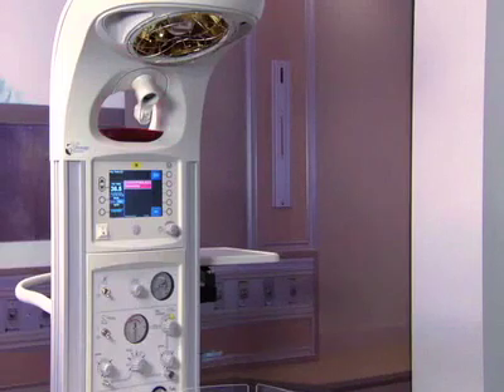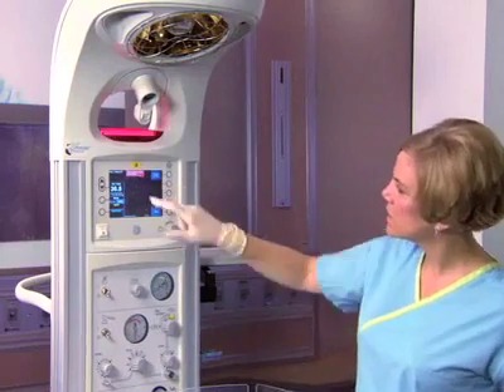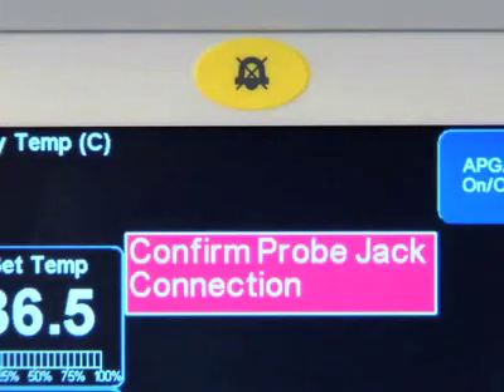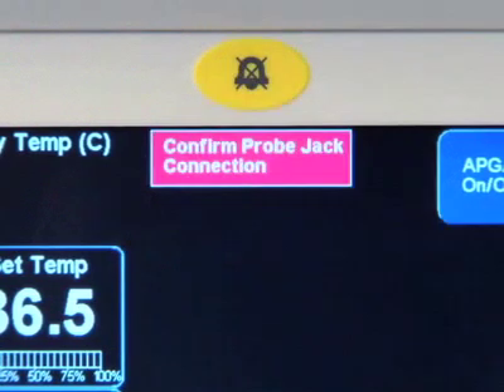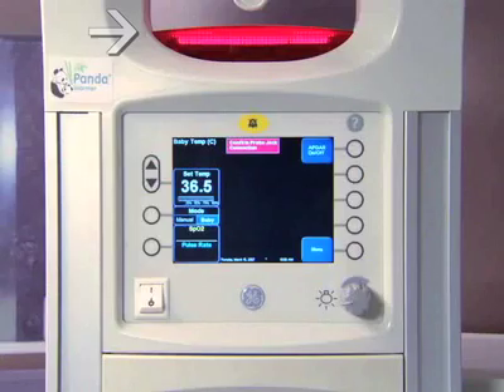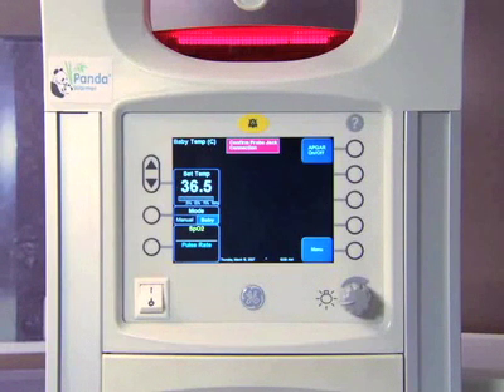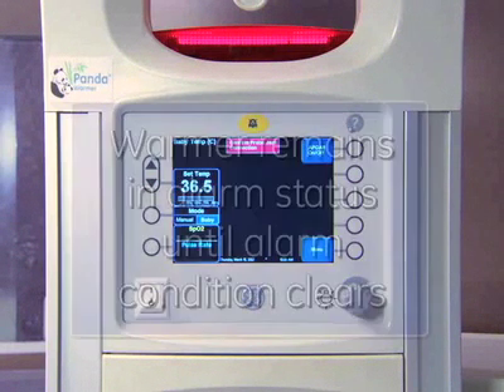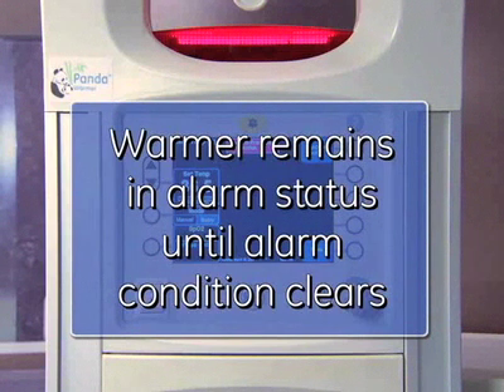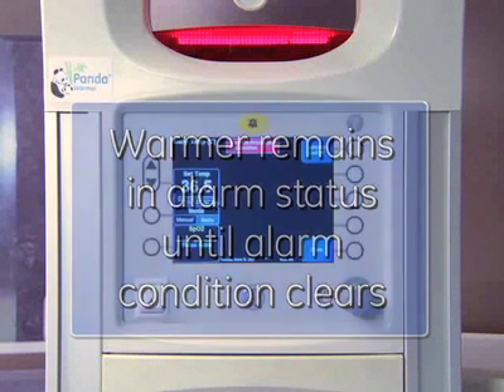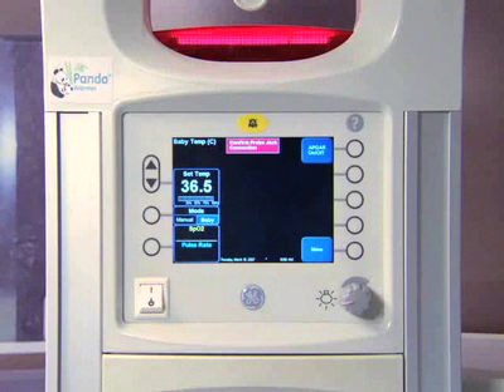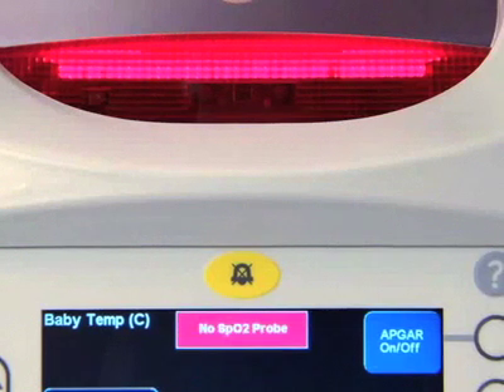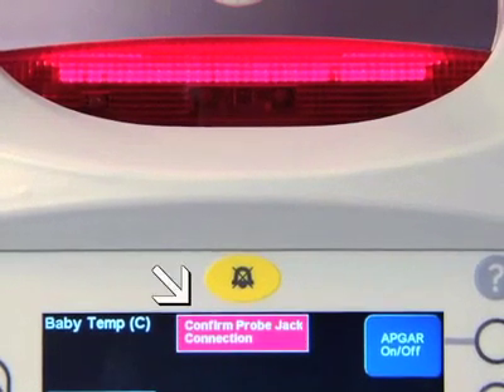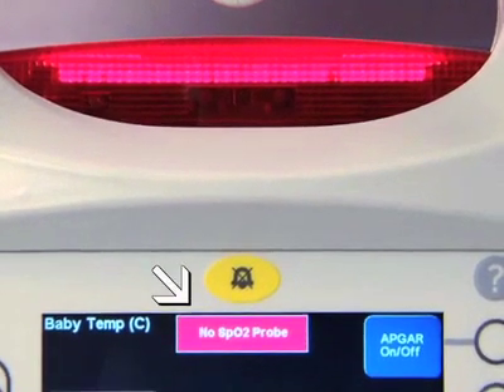To silence the alarm, press the yellow key at the top of the control panel. When you silence an alarm, the text message gets smaller and moves to the top of the screen. The light goes from blinking to solid. When the alarms have been silenced, the audio tone is temporarily turned off, but the warmer remains in alarm status until the alarm condition clears. The audio tone will resume when the silence period expires, which varies with the alarm type. If there are multiple alarms, the text messages alternate every 2 seconds.